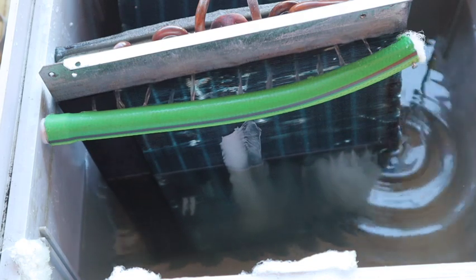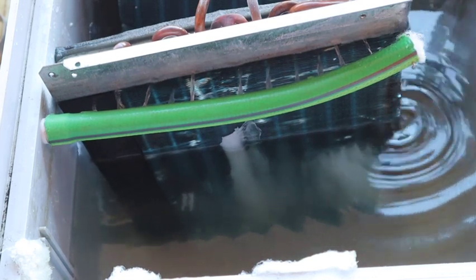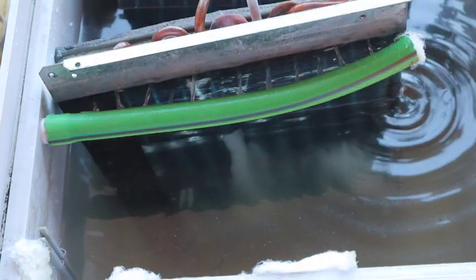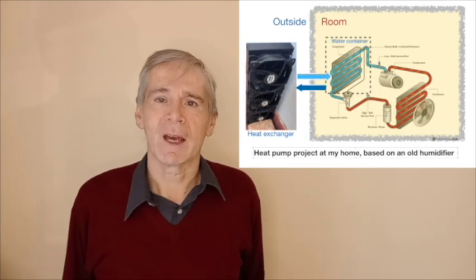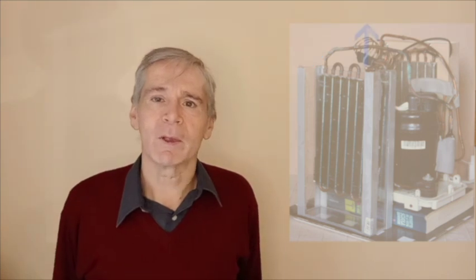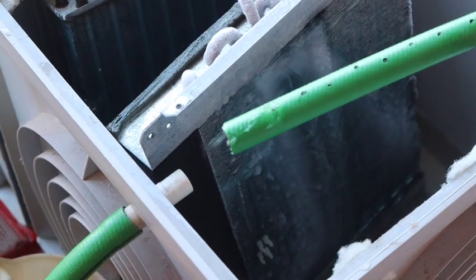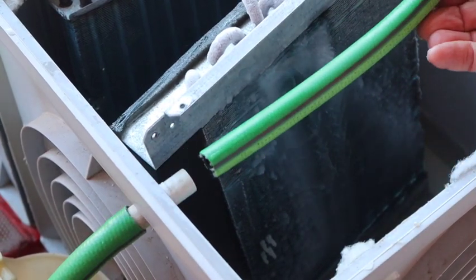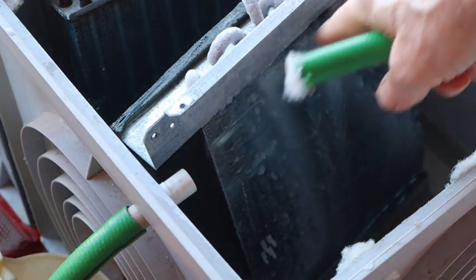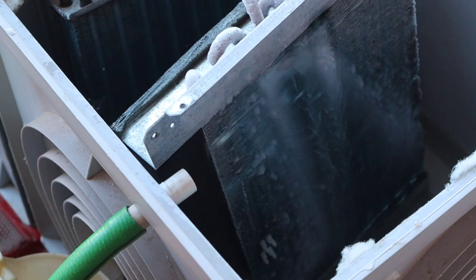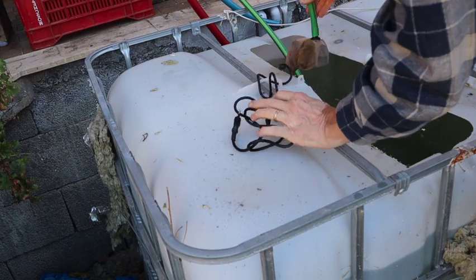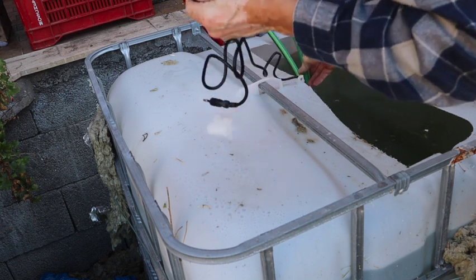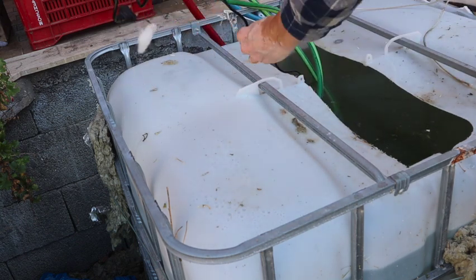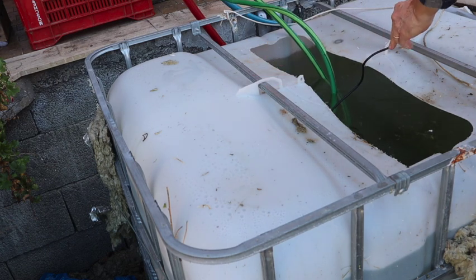What is better to avoid ice on the evaporator, a shower or a bath? With a bath, be sure that there is constant flow through the evaporator. Note that it enters the bucket at the other side of the heat exchanger, compared to the water exit, where the water goes out of the bucket. This will create a water flow across the heat exchanger and ensure that it will not freeze. With a shower, it seems that there is a good flow through the evaporator, and supply water will also melt away the ice layers, if warm enough. Supply this water as warm as possible, so use stratification in the big cold tank and place the pump where the temperature is maximum, that is just under the surface. We will see that in more detail now.